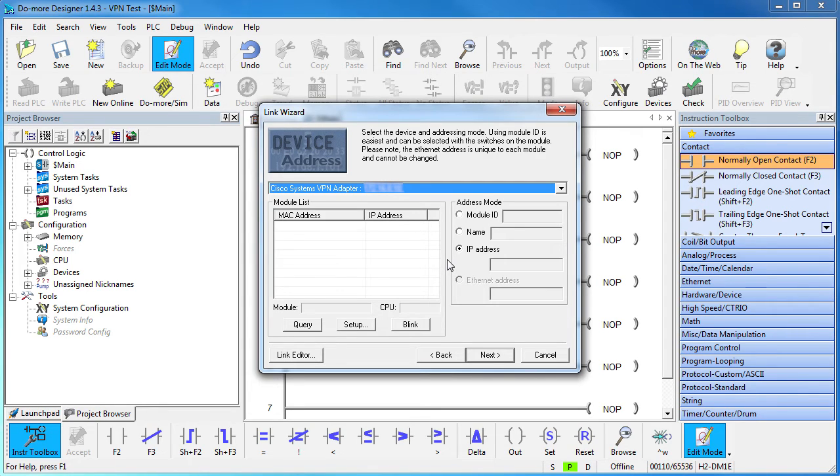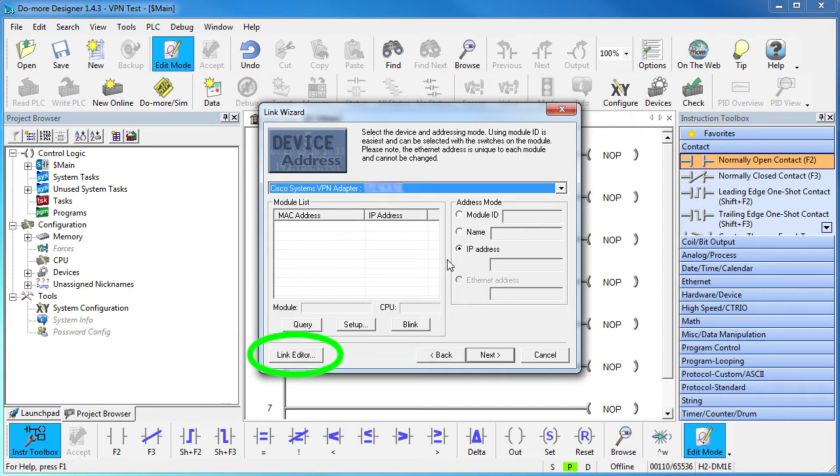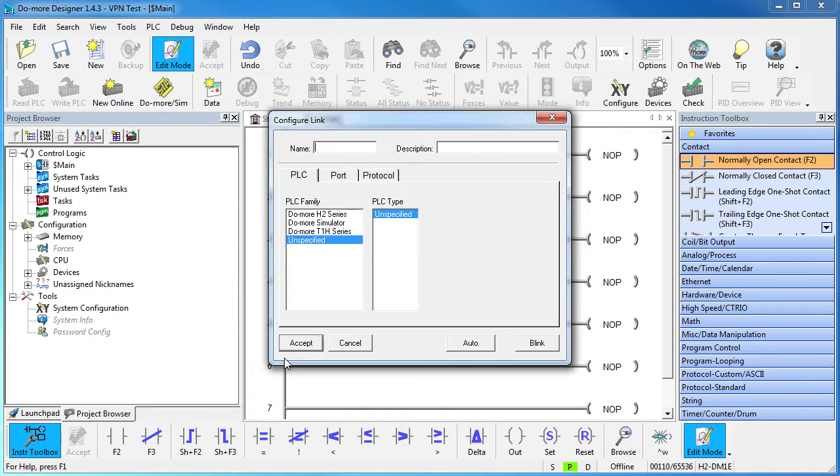Well, because you can't auto detect Do-mores on the other side of a VPN. The stuff Do-more Designer needs to detect those PLCs is hidden by the mechanics of the VPN. So we hit this link editor button, which we could have hit in the previous step, to tell Do-more Designer how to find the Do-more PLC.